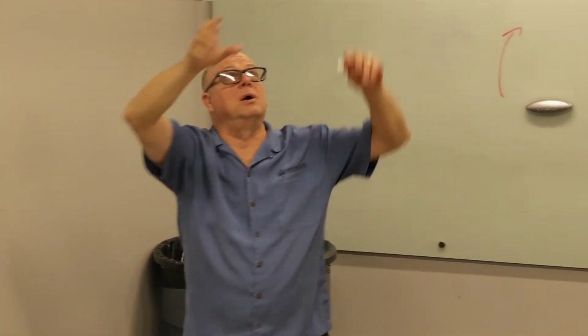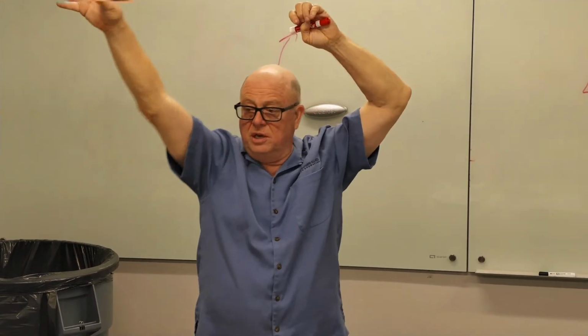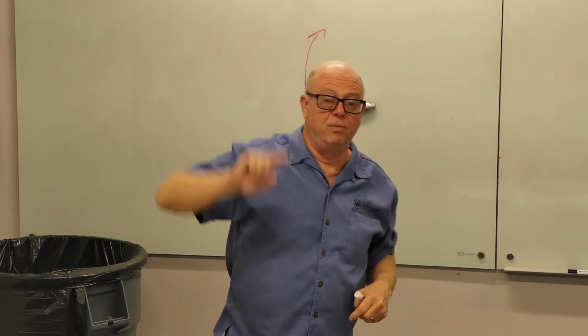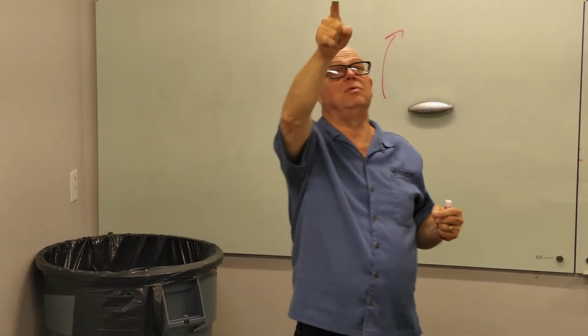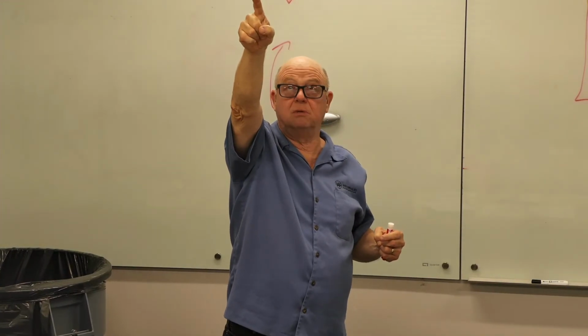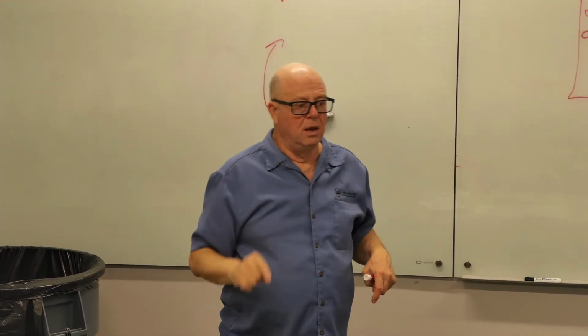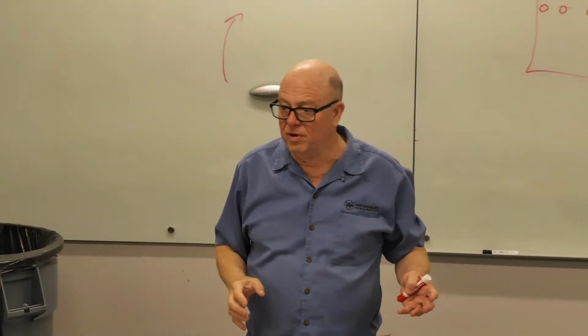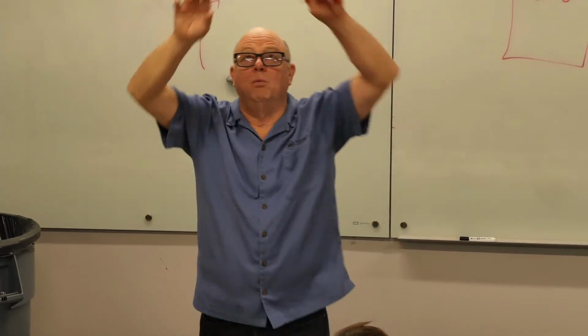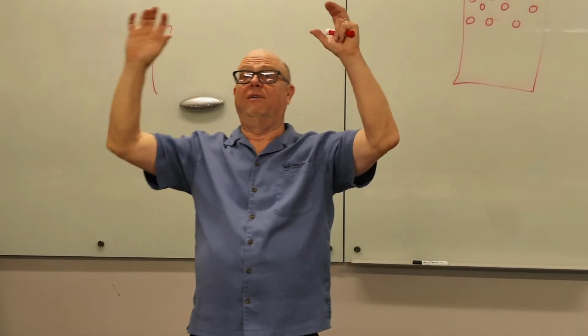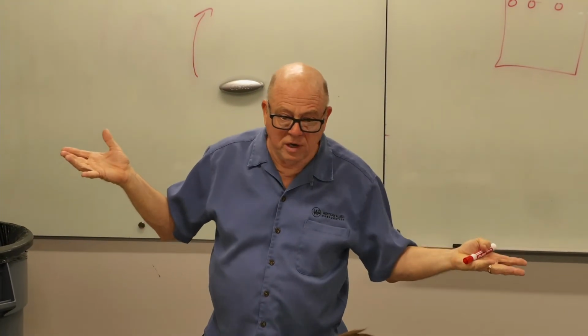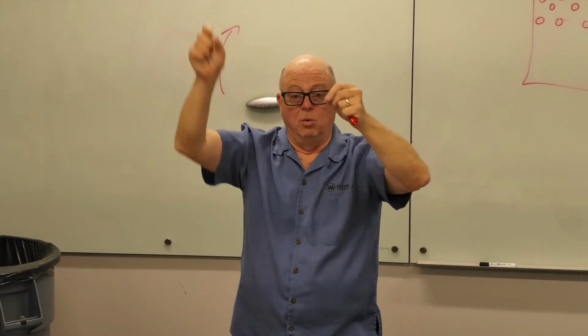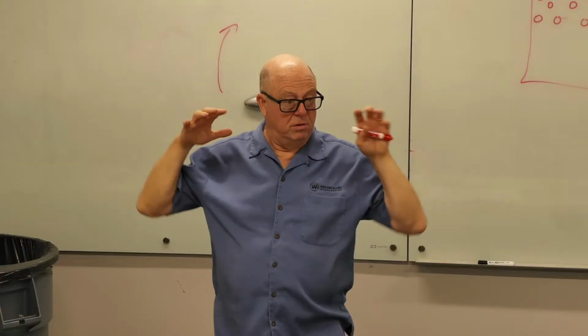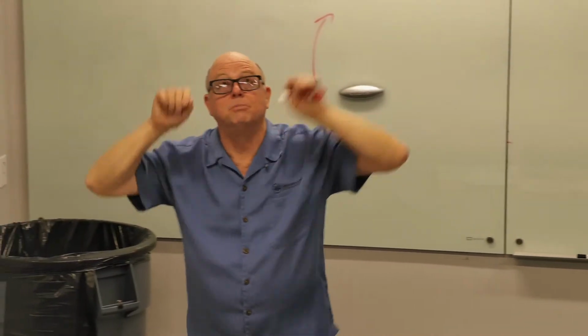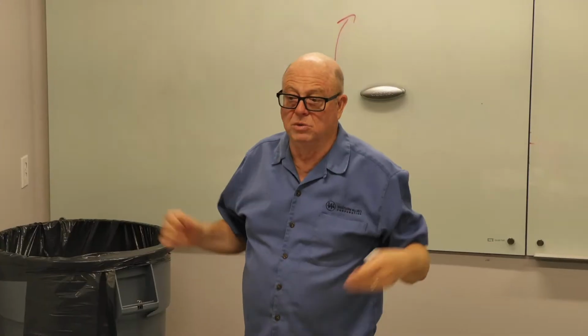And then we'll get some return air, egg crate grill, whatever, and we're pulling air out of the room through the ceiling plenum. And that's going to include the heat from the lights. Now, although these are putting all the heat into the space. See how the bulb is here? That's a lot more common with LED now that we've got LED. Used to be, if it was any kind of fluorescent, and you still see a lot of fluorescent lights out there, it would be a housing with holes in the top so that the heat could rise from the bulbs up into the ceiling plenum. That was the typical, okay?